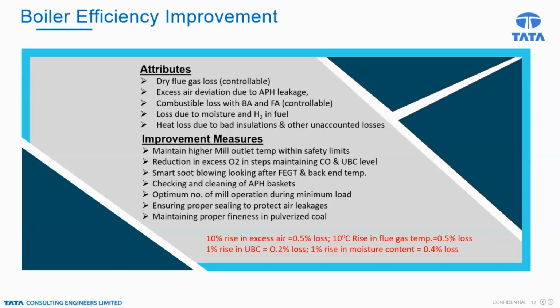Ensuring proper sealing to protect against air leakages, maintaining the proper fineness in pulverized coal. If we take care of these measures during operation, obviously we will have better boiler efficiency. To give an example, a 10% rise in excess air will have a 0.5% increase in loss. A 10°C rise in flue gas temperature will have a 0.5% increase in loss.